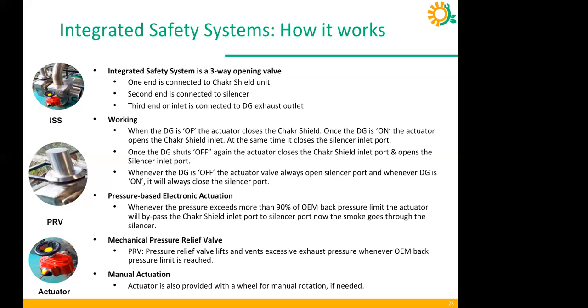Since it's a retrofit, obviously a retrofit has back pressure. What we claim is that our back pressure will always be within the allowable limit set by the OEMs. If I take an example, OEMs generally define 7 to 10 kPa as the major allowable back pressure limit, depending upon the various OEMs available. Our device will always function below 7 kPa.